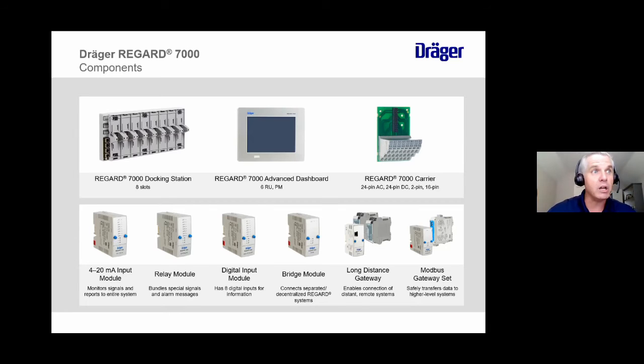We have bridge modules, which would allow you to basically connect legacy old Regard systems to the new Regard 7000. And how you do that is through one of these bridge modules. We have long distance gateways that allow you to connect up to, I think, 30 kilometers away through fiber optic cable, different Regard systems into a central Regard 7000. And we also have Modbus gateway sets for Modbus inputs and Modbus outputs as well. And that's very important for the networking stuff we can do with this guy.